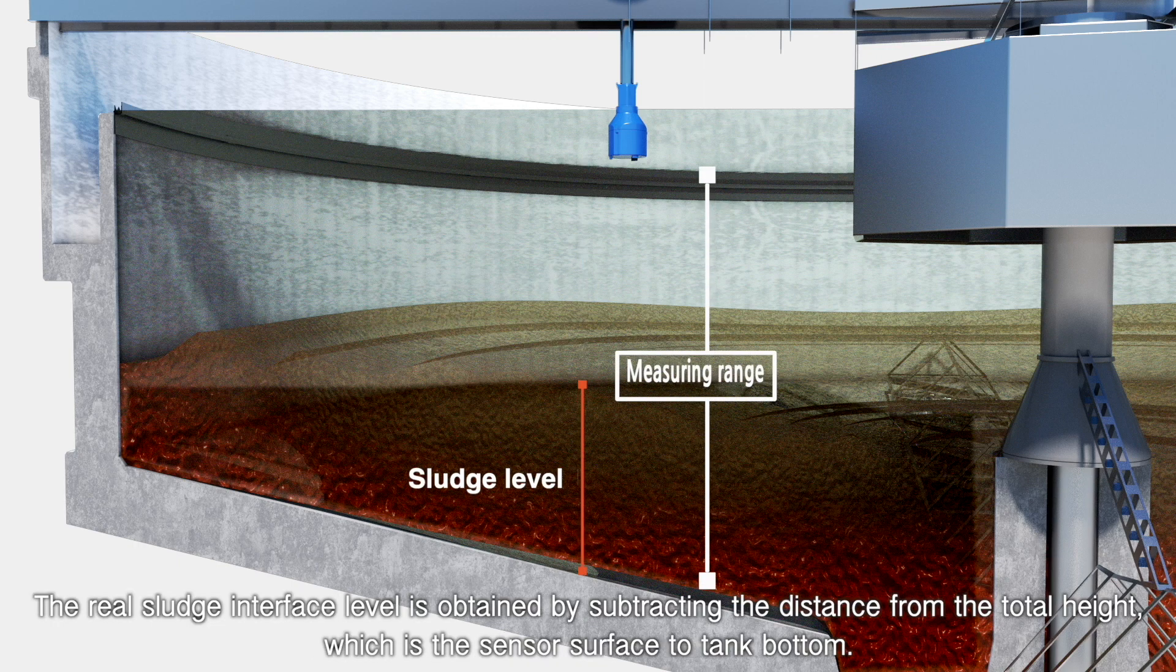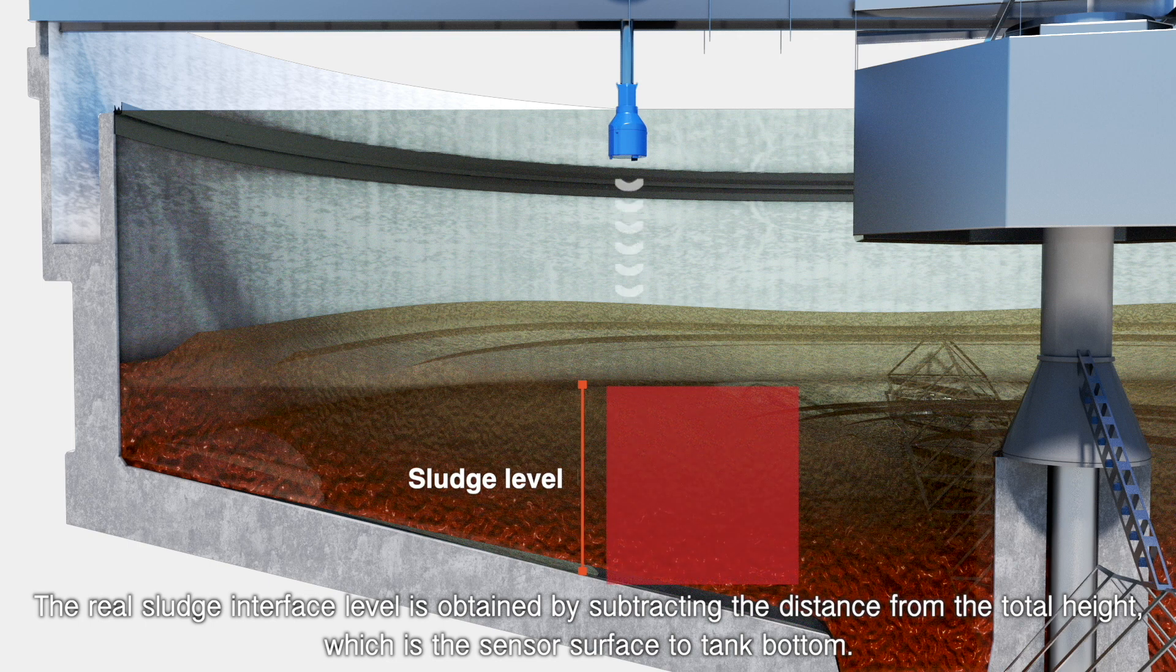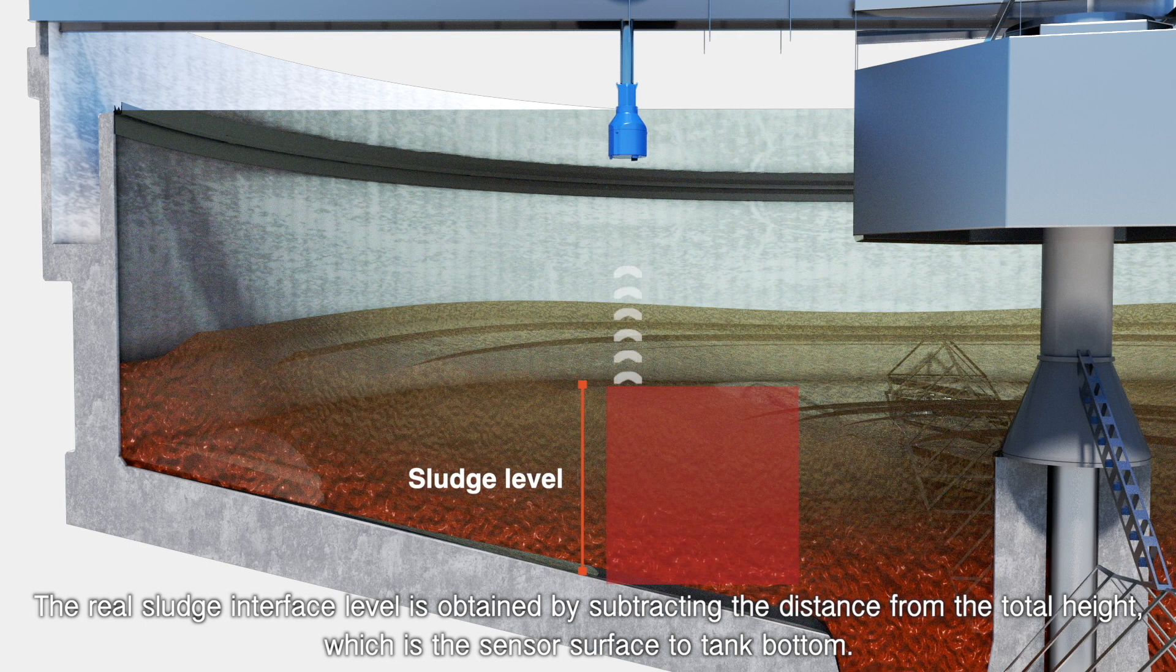The real sludge interface level is obtained by subtracting the distance from the total height, which is the sensor surface to tank bottom.